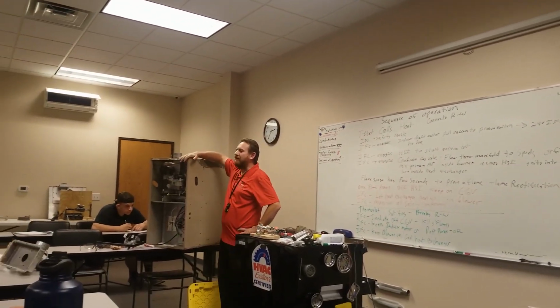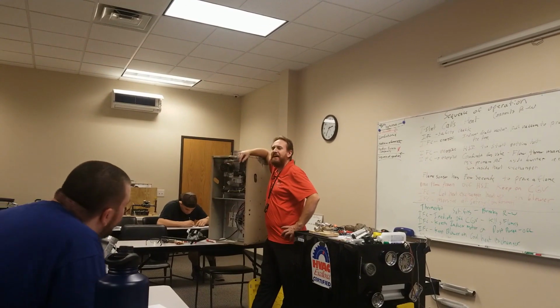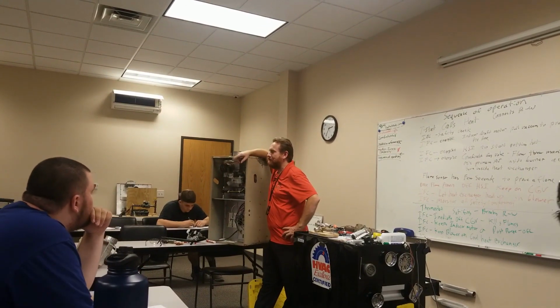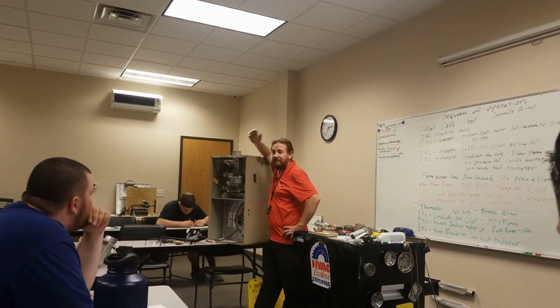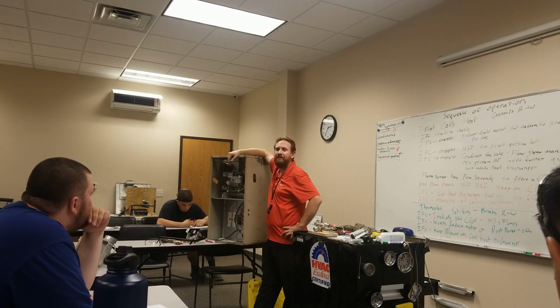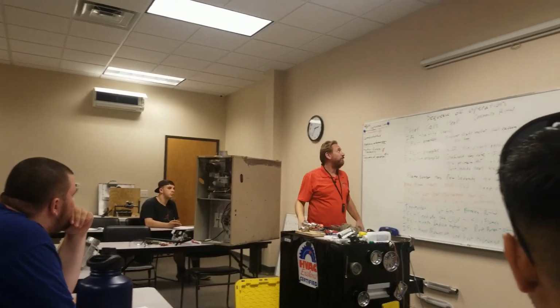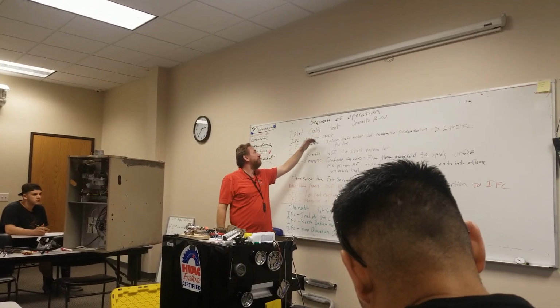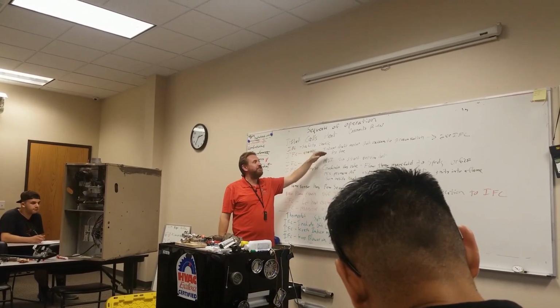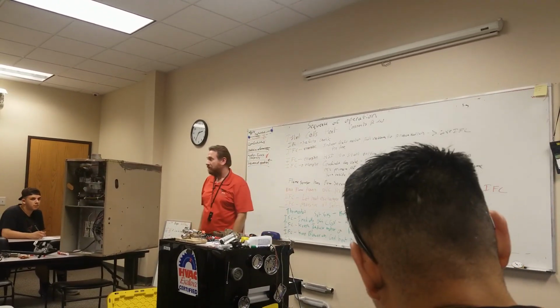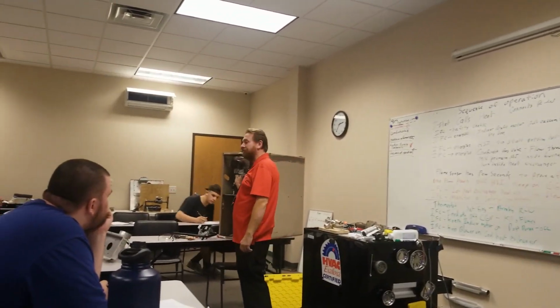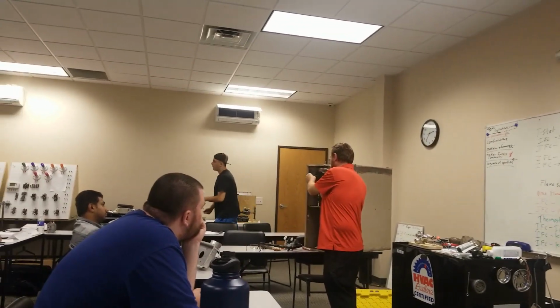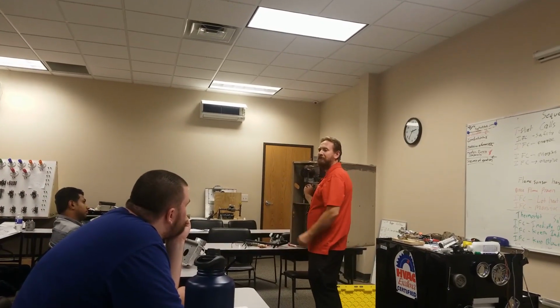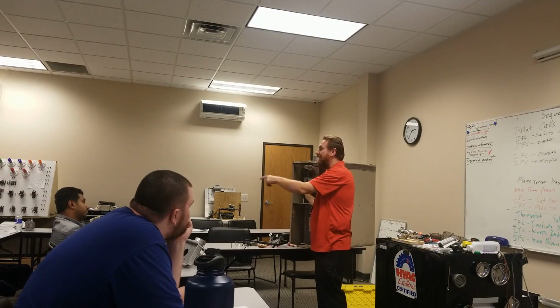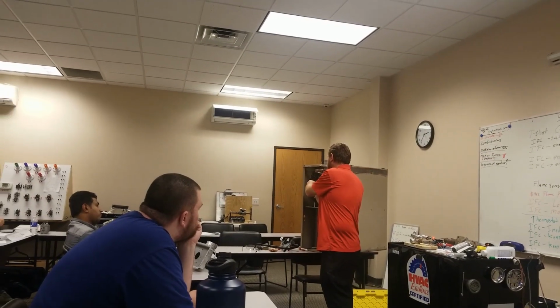Now, this sequence of operation is your way of diagnosing the system. You go to the thermostat, you have a call for heat. This fan motor doesn't come on. Right? Well, the thermostat calls for heat, connects R and W, there's a safety check, and then it energizes the inducer fan motor. So one thing you can do is check to see if you're getting voltage here. Pull this plug out, put my voltmeter here. I'm getting voltage there. What's the problem? Bad motor, yes.